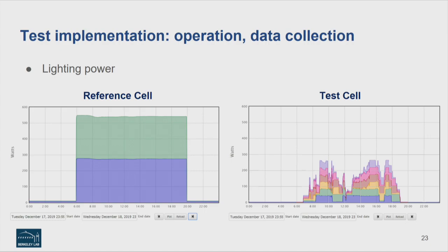Lighting power is really the biggest impact from this package. These are stacked graphs, so the topmost one represents the sum of all the lighting wattage in the space. We're almost up at 600 watts for the entire facility in the reference cell, and much lower in the test cell. It's dynamic throughout the day in the test cell, because as occupants come and go, the fixtures turn on and off, or at least dim, and then dim further with daylight harvesting.